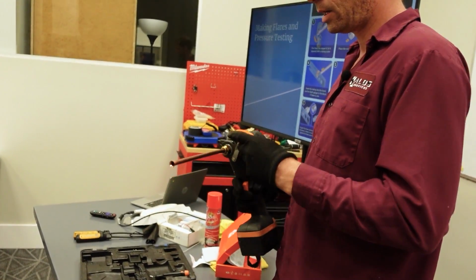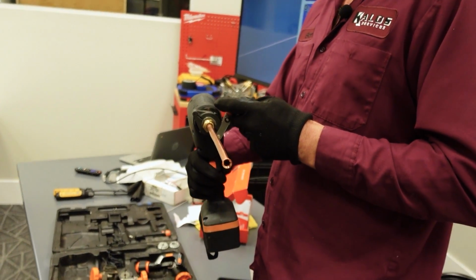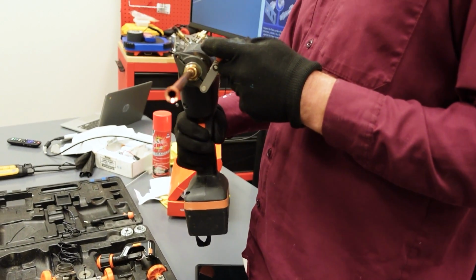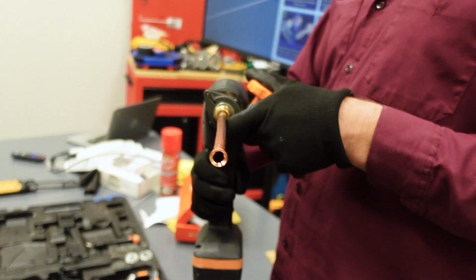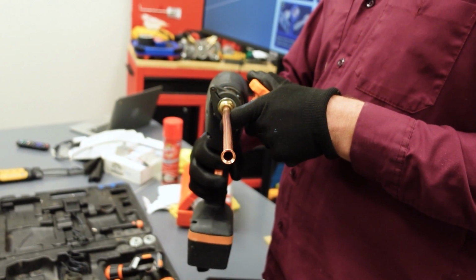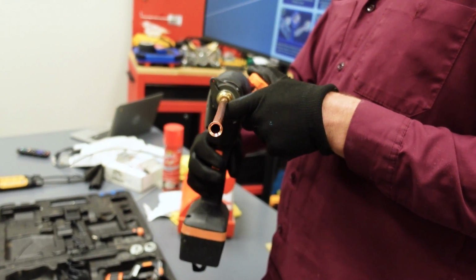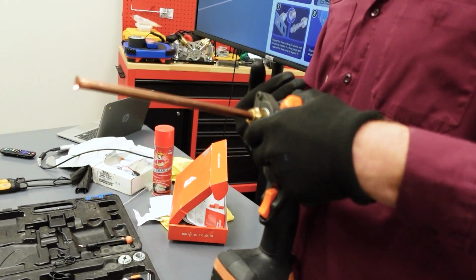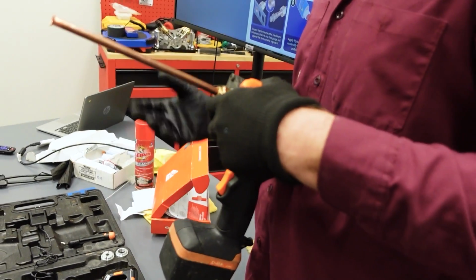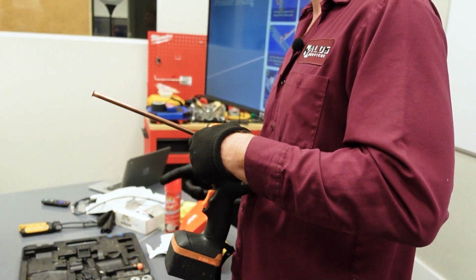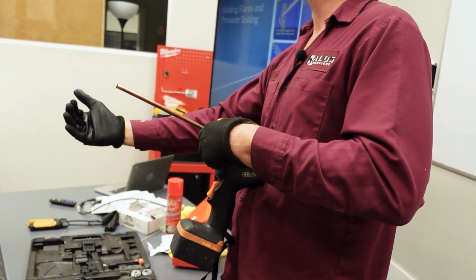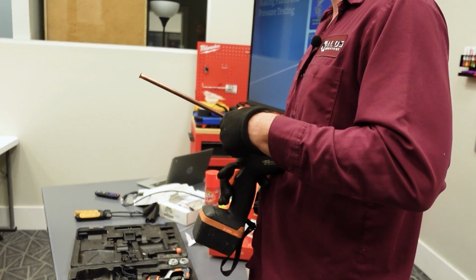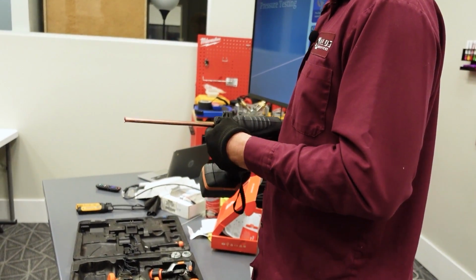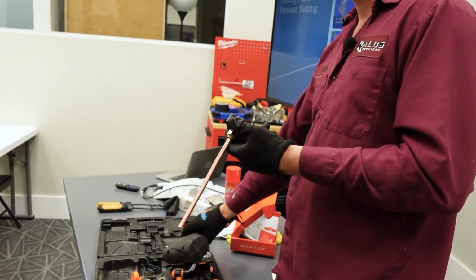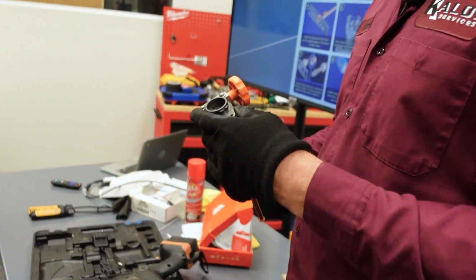So then I go forward into the flare. You can hear when it's finished, and then back it out. If you want to make sure, when backing it out, take it all the way back. Another feature with the newer gun is you just push the button and it takes it all the way in and back out for you, so you don't have to control it manually. That's the newer version, and then your flare joint.